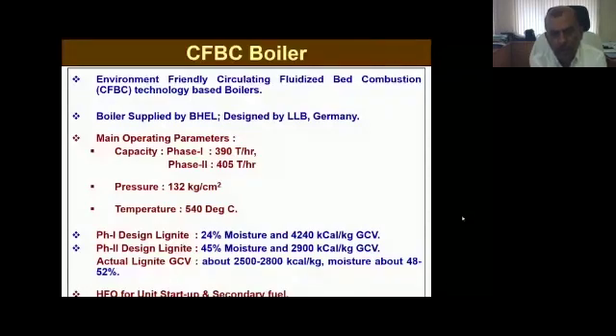Then the capacity, as already mentioned, considering a 125 megawatt unit size, is 390 tons per hour. In phase 2, we took some margin considering the degradation in the fuel. The pressure and temperature are not very high - if you compare with supercritical and ultra-supercritical, it is only 132 kg and 540 degrees.